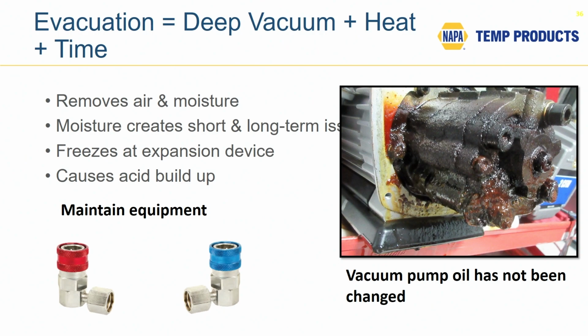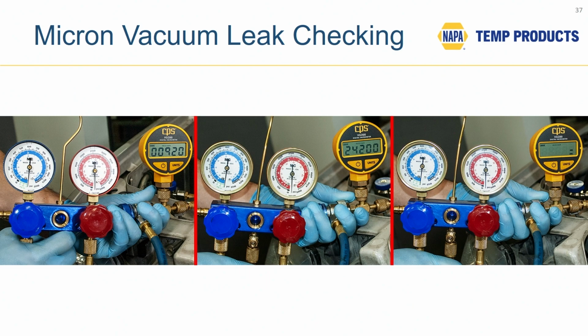Couplings get connected and disconnected hundreds of times a season. They're a common source of little micro leaks that prevent you from pulling a deep vacuum on the system. Now, speaking of vacuum, you can see in these three pictures that I've got a conventional manifold gauge set connected up to this vehicle, and teed in series with the low side line, I've got a micron vacuum gauge. That yellow gauge there is a micron vacuum gauge.